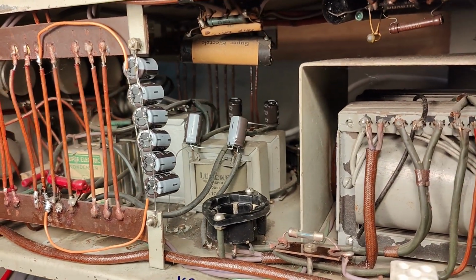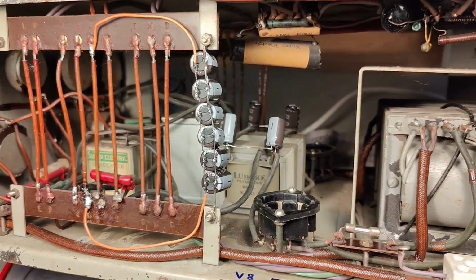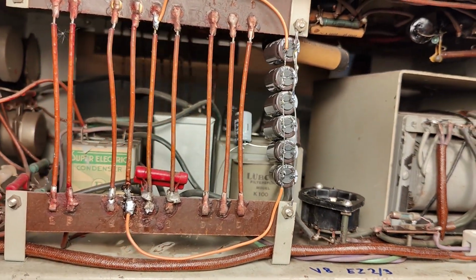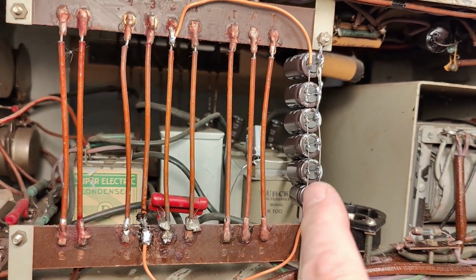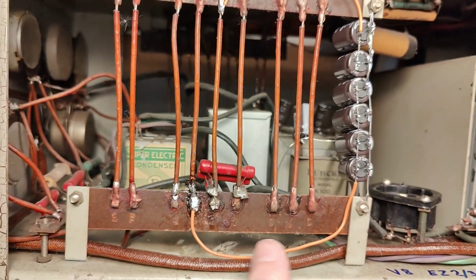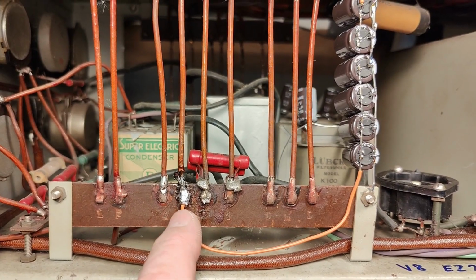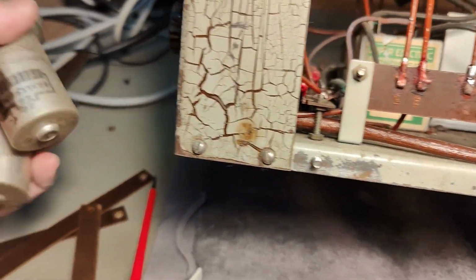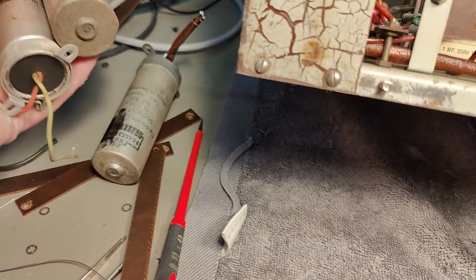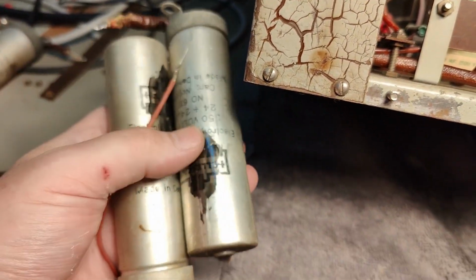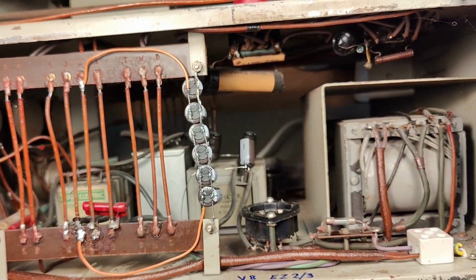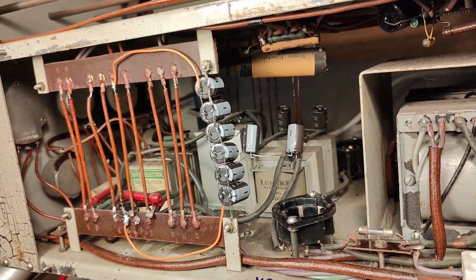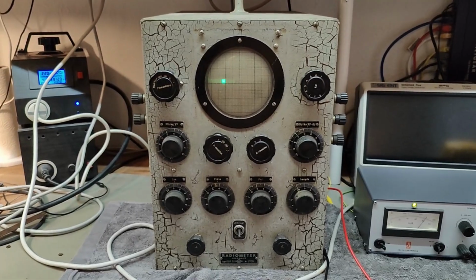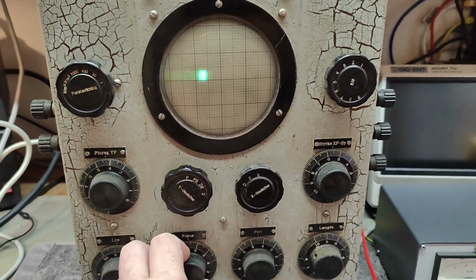Perfect! So now I replaced all the capacitors with new modern teeny weeny sized capacitors, but they're actually a lot better. And I am back to the original value with 4 of them in parallel on voltage 3. So that is the same as 2 of those 2. Remember, the one that was shorted, they just took out, right? So it's going to be real fun to see how this works out. And what do you know? It is now sweeping.